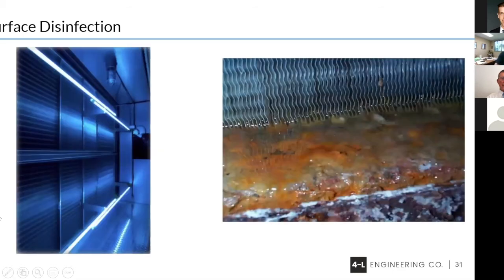Next slide. Here we can see the UV lighting on the face of a coil, and you can look at the shine factor. They're somewhere around 12 inches off the face of the coil. If you get it too close to the face of the coil, I don't get the shine to cover the entire surface. The second thing is that I'm on the wet side of the coil, so the air is moving from the left of that coil to the right. It'll carry the moisture off and hit the light, and of course, I put water onto the light. It's not a good effect. To the right-hand corner here is some of the buildup that exists in drain pans that we control with UV lighting. Next slide.